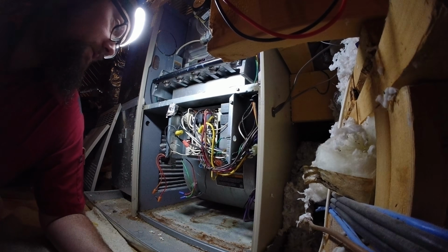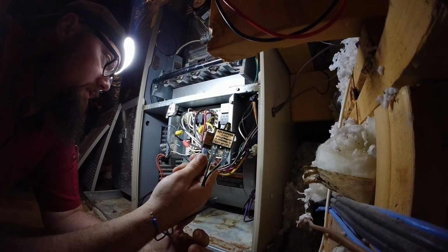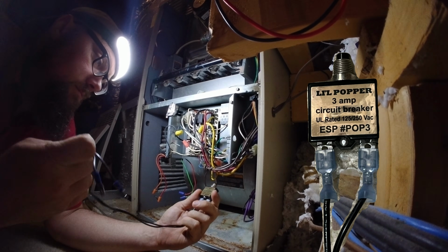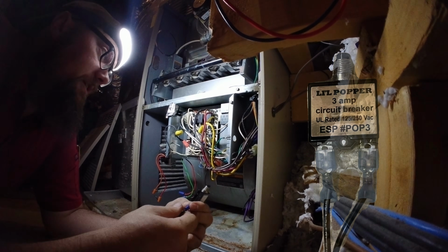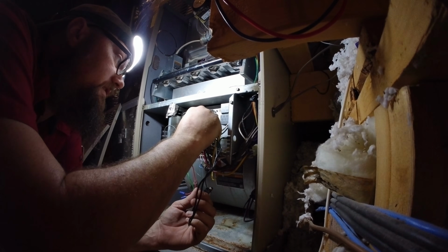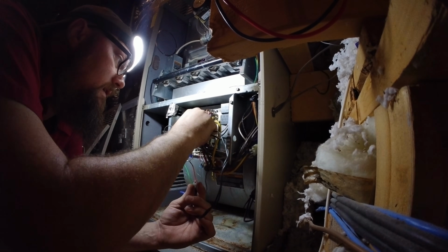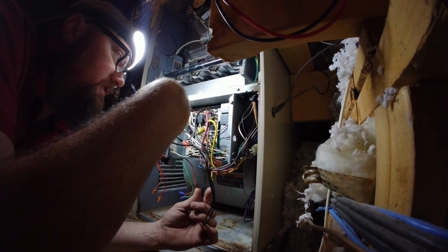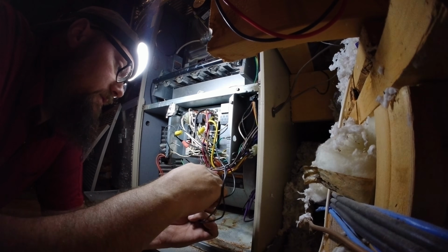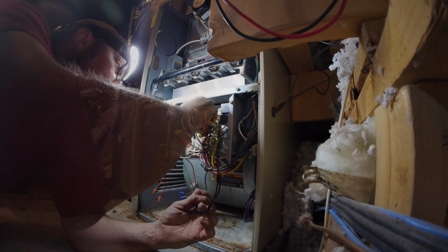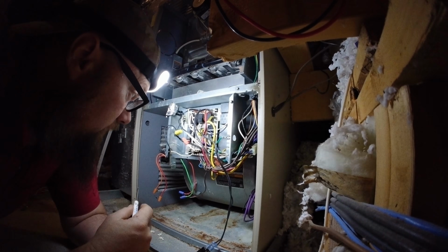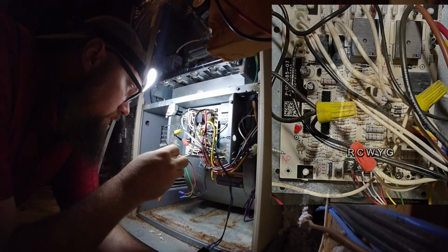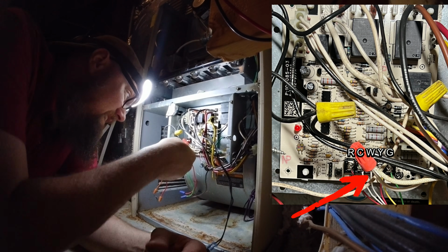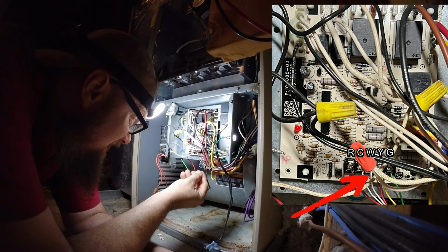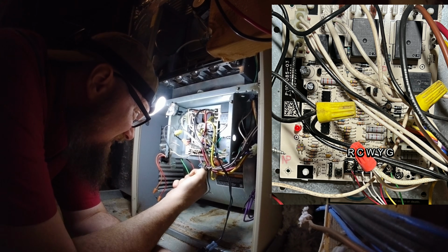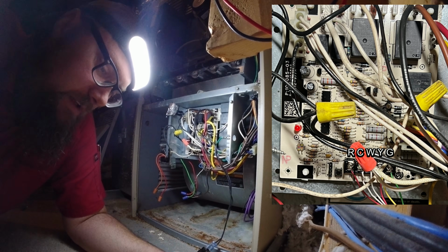Just to check and see whether it's a nuisance short or not, we have a little 3 amp popper. It's like a little miniature circuit breaker, essentially. That way we're not wasting fuses. But we'll plug this guy in place of where our fuse goes. So everything did start up. We will disconnect our furnace wire, let it shut back down.